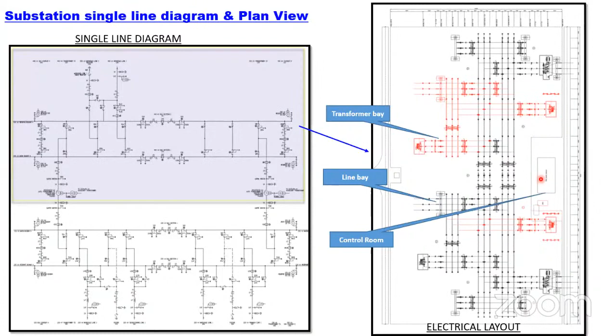Then if you enlarge this single line diagram, you will get the representation of the layout. If you look at the layout, you can see all the red lines are the power transformers. The power transformer is in a rectangular shape. I have also represented the transformer bay, and this is the line feeder bay, and you can see this is the control room. The physical layout, the length and breadth of the station, will be maybe 150 meters by 100 meters, and basically it is an air insulated switchgear substation. The control room helps to monitor the whole station. The operators are located here. Okay, then let's move to the next slide.